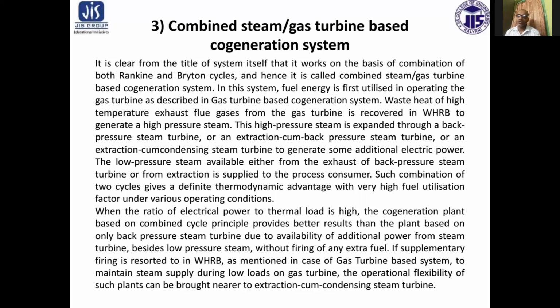Waste heat of high temperature exhaust flue gases from the gas turbine is recovered in a waste heat recovery boiler to generate high pressure steam. This high pressure steam is expanded through a back pressure steam turbine, or an extraction cum back pressure steam turbine, or an extraction cum condensing steam turbine to generate some additional electric power. The low pressure steam available either from the exhaust of the back pressure steam turbine or from extraction is supplied to the process consumer.